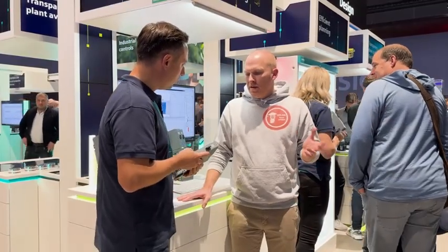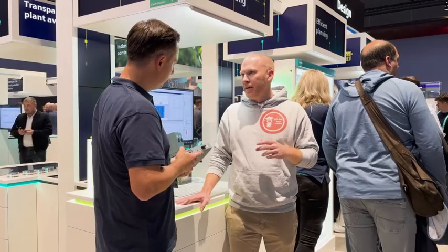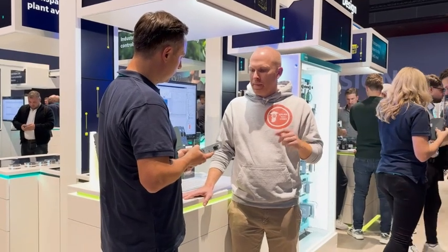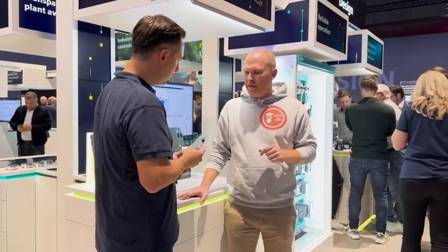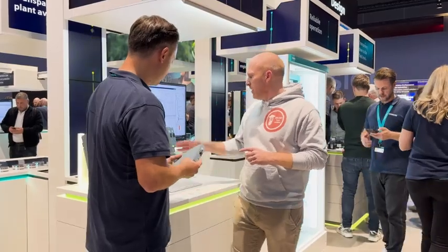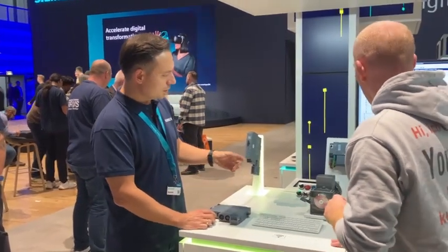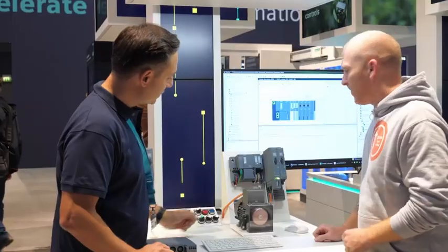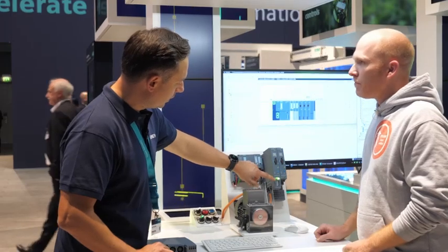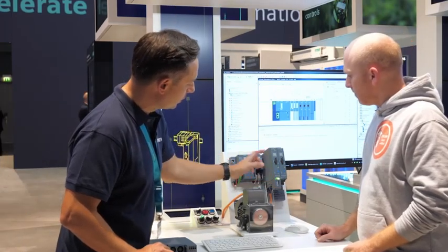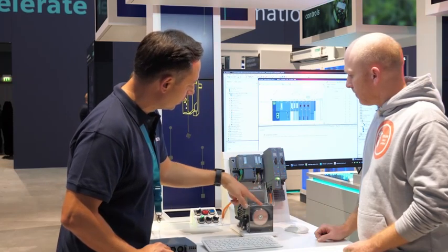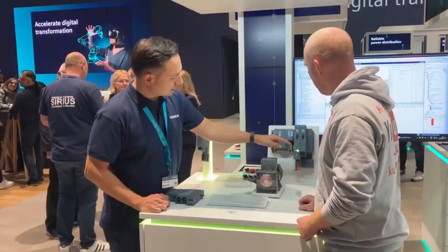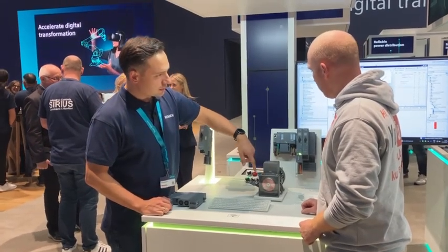Because this e-starter lets through less force than a normal short circuit current on a normal MCCB, thanks to the fast tripping. You talk about the reset possibilities. Yes. Maybe we can make a short simulation here. Sure. So we can see the motor is running, and as I understand, green means always okay at Siemens, right? That's correct. Here in the lower part we see the display of the direction of rotation of the motor. So we see now the motor is turning right. I see you have counterclockwise and clockwise. Clockwise, exactly. Now the motor is running and let's say a short circuit happens.